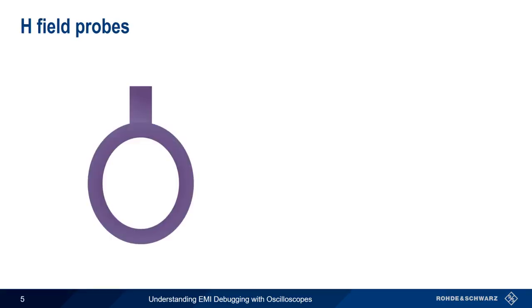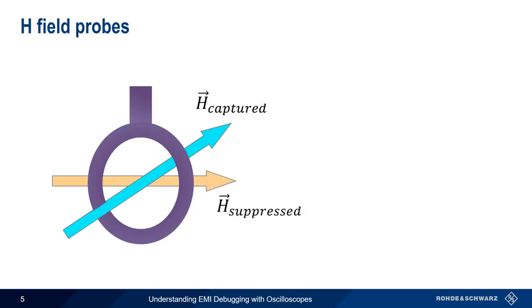H-field probes are typically in the shape of a loop. Maximum response occurs when the loop is at 90 degrees to the signal, or when the magnetic field is passing through the loop. Minimum response occurs when the loop is parallel to the signal.